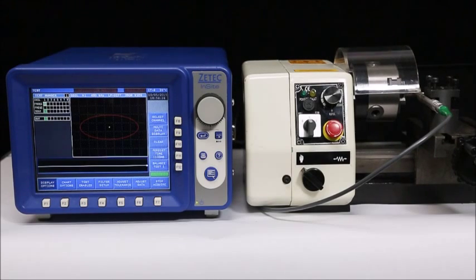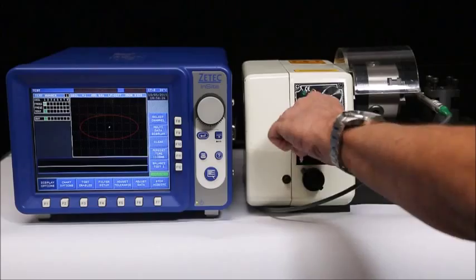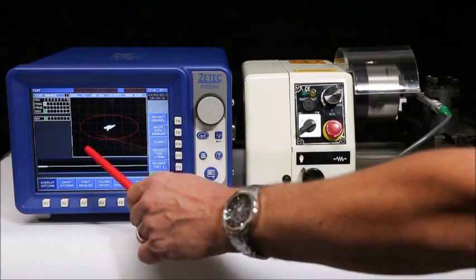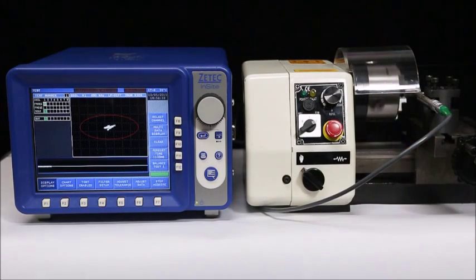I'm going to turn on the lathe and scan across the EDM notch. What you see on the instrument is normal material noise that's witnessed when we scan across the carbon steel material.